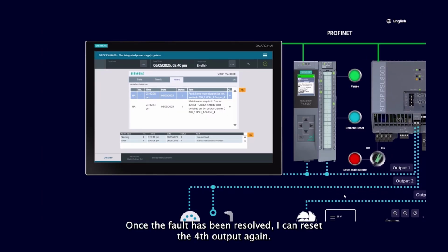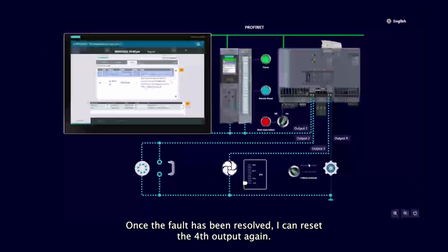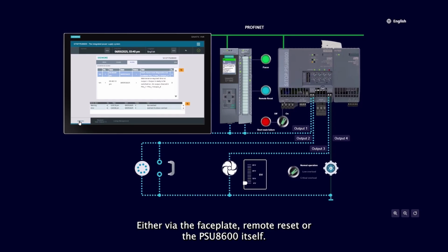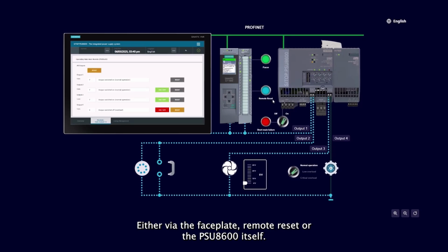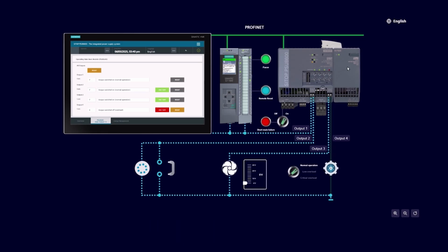Once the fault has been resolved, I can reset the fourth output again, either via the faceplate, remote reset, or the PSU8600 itself. I now use the common reset.